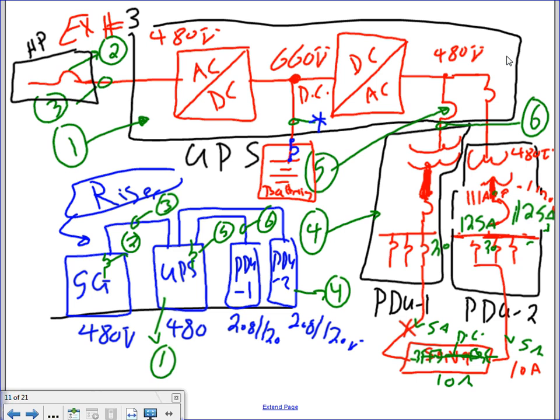First, I need to go size the UPS system. Second, I need to size the overcurrent protection device on the primary side. Third, I need to size the feeder. Fourth, I need to go size my PDU that's coming from the UPS system. And fifth, the overcurrent protection device for the PDU. And number 6 will be the feeder that's coming to the PDU.